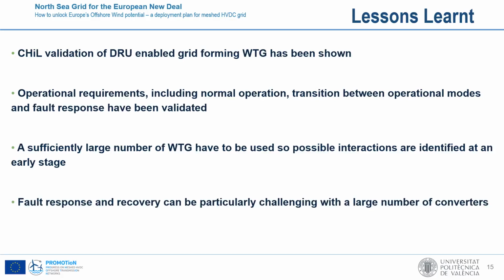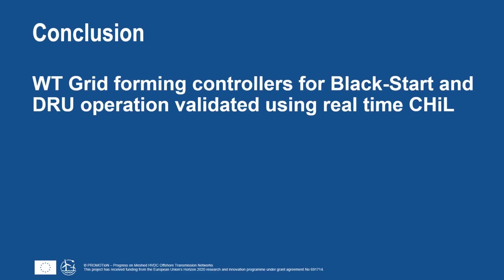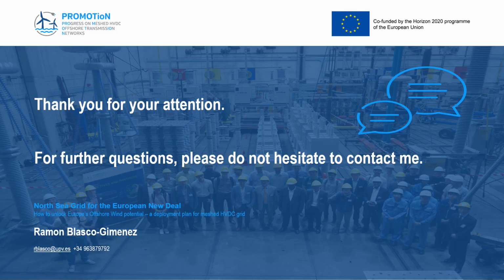Finally, it is worth stressing that fault response and fault recovery can be particularly challenging with a very large number of grid-forming converters. The main conclusion is that we have carried out a control hardware in the loop detailed validation of wind turbine grid-forming controllers for black start and for DRU operation, and therefore we have increased the TRL of such controllers. Thanks a lot for your attention, and I'll be happy to answer any questions you may have.